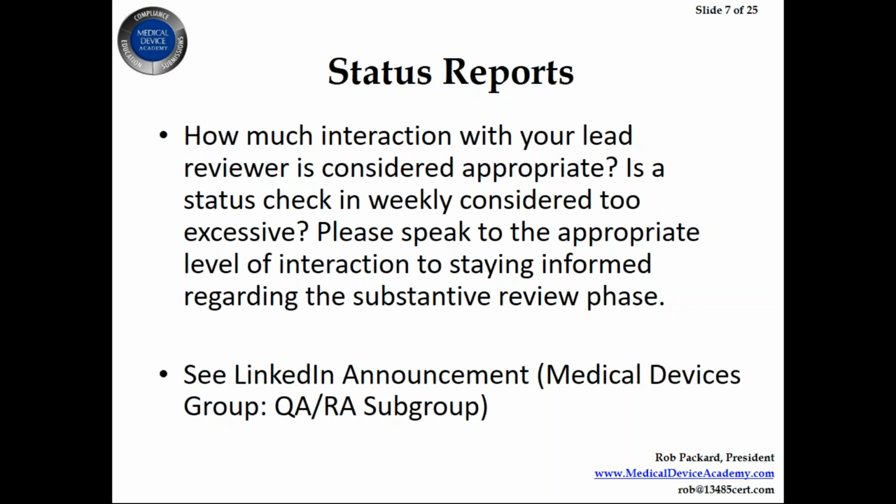So if you're doing a 510K, you have that first step, then the second step is the RTA review. That's usually day 14, day 15, you're getting an RTA response, whether it was accepted or not. And then between day 15, when the RTA review is done, and day 60, when they're supposed to make a decision as to whether it's going to be an interactive review or request for additional information, there's 45 days of time that you may hear absolutely nothing. That's called the substantive review phase.